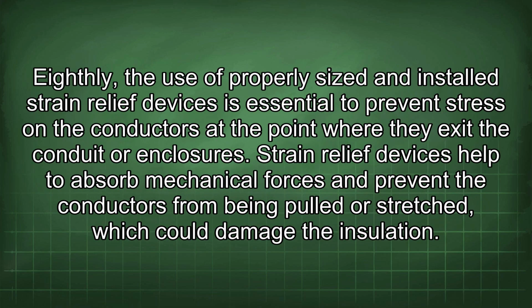Eighthly, the use of properly sized and installed strain relief devices is essential to prevent stress on the conductors at the point where they exit the conduit or enclosures. Strain relief devices help to absorb mechanical forces and prevent the conductors from being pulled or stretched, which could damage the insulation.